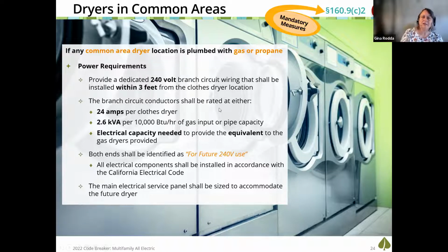Because here I'm going to do that 240 volt branch circuit at each dryer location. And then I'm going to look at, for the branch circuit conductors, what is the capacity of the drying going on in the space, or the capacity of that gas piping system. And I am going to have to make sure the electrical capacity is available to meet the equivalent of the gas dryer capacity. This is a big deal when we're sizing our transformers and our electrical rooms to serve these buildings and these properties.